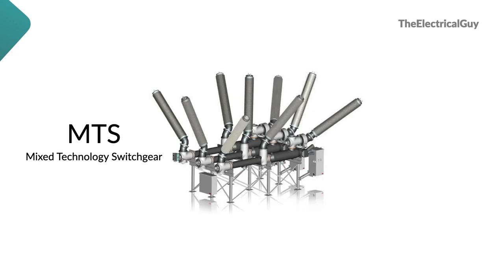You can see on your screen, this is the mixed technology switchgear. This is called one bay. One bay will consist of your circuit breaker, disconnector, current transformer, voltage transformer, and in some cases a lightning arrester. And the top portion, what you can see here, are the bushings. The busbars will come, and the busbar connection will be given to these bushings. This is the combination of AIS and GIS, which is called MTS or mixed technology switchgear. Clear? So these are the types of switchgear available currently in the market, and you can choose one of them.